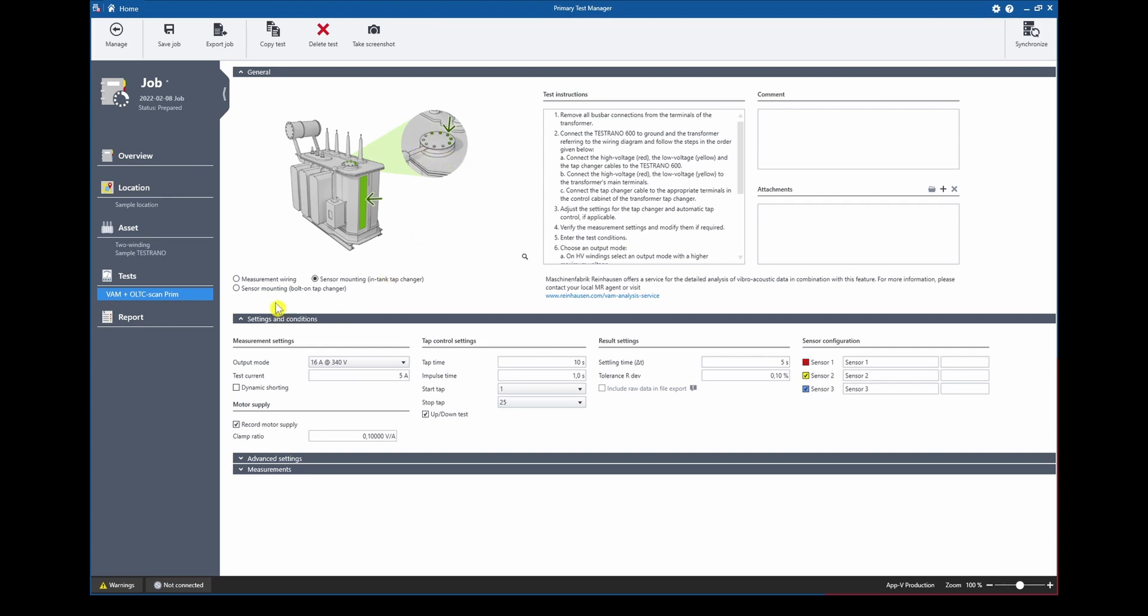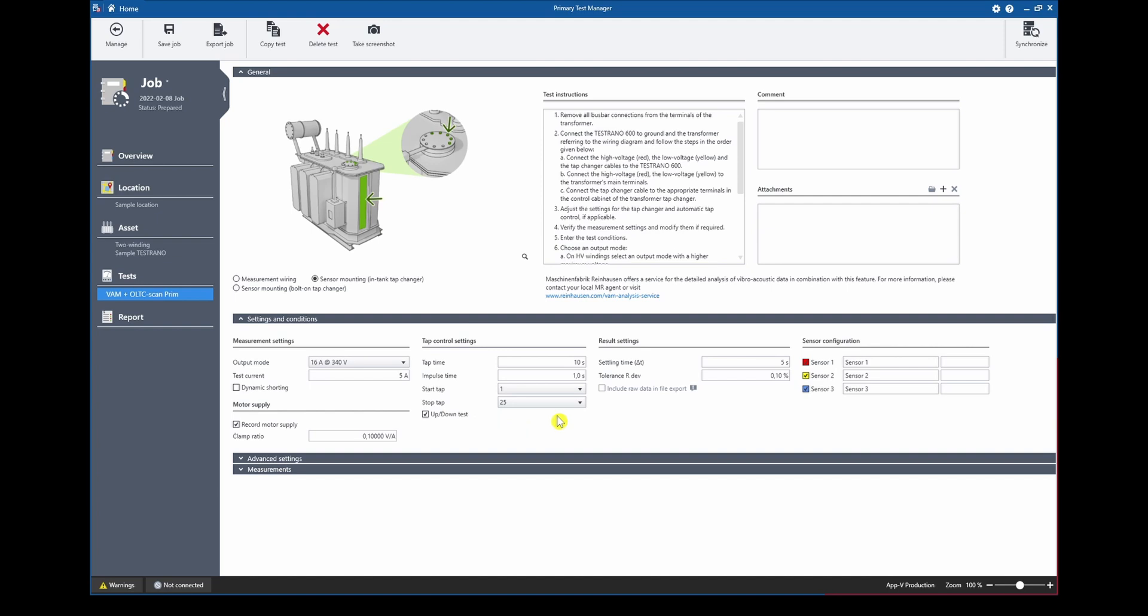Going down to the settings we can see that those are very similar to the single-phase DRM tests, including the test current and output mode and the option to record the motor supply current. We can select how the tap control is operating so we can select the start and the stop tap of the measurement and new to this test on the right hand side is the sensor configuration.